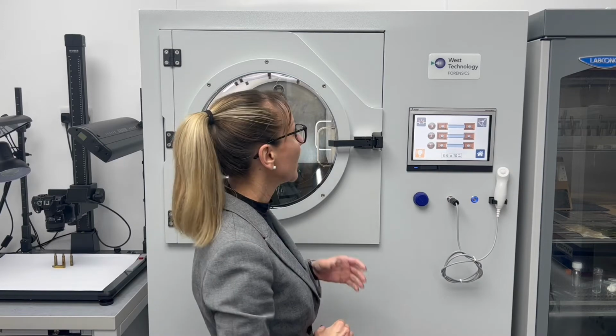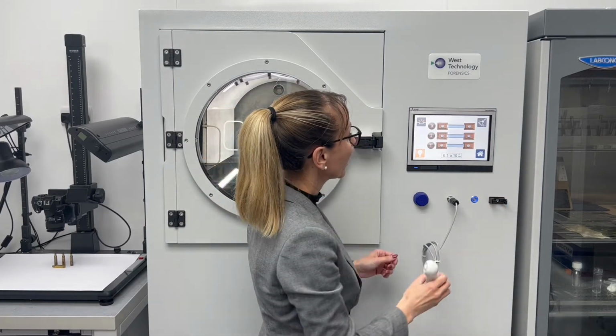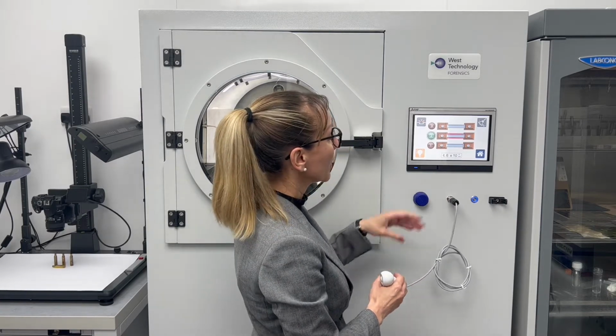Currently, we cannot see any color change on our exhibit in the chamber. To cause some color change, we need to use zinc. So to evaporate the zinc, we need to activate the board first by pressing number two, and then the system will adjust the vacuum level in the chamber automatically.